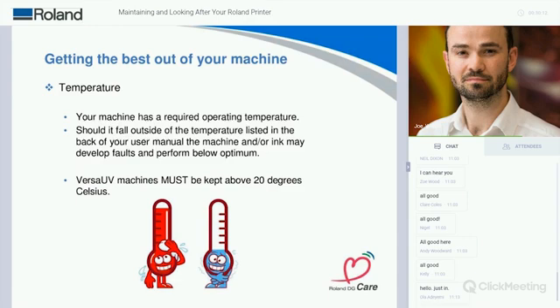Versa UV machines are a little different — they require an operating temperature of 20 degrees Celsius, and I recommend they stay at that temperature all the time. Otherwise, the machine will struggle to clean itself properly, and you'll likely arrive to an error on screen saying the temperature is too low. That's not good for anyone, since you then have to wait for the machine to warm up, and it's not good for the machine either, as it can't operate correctly.